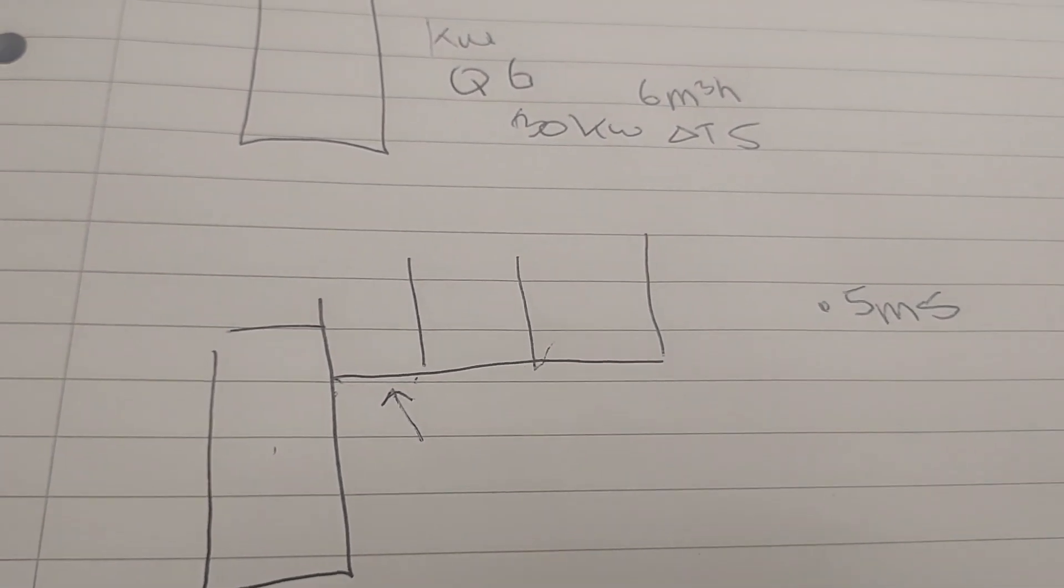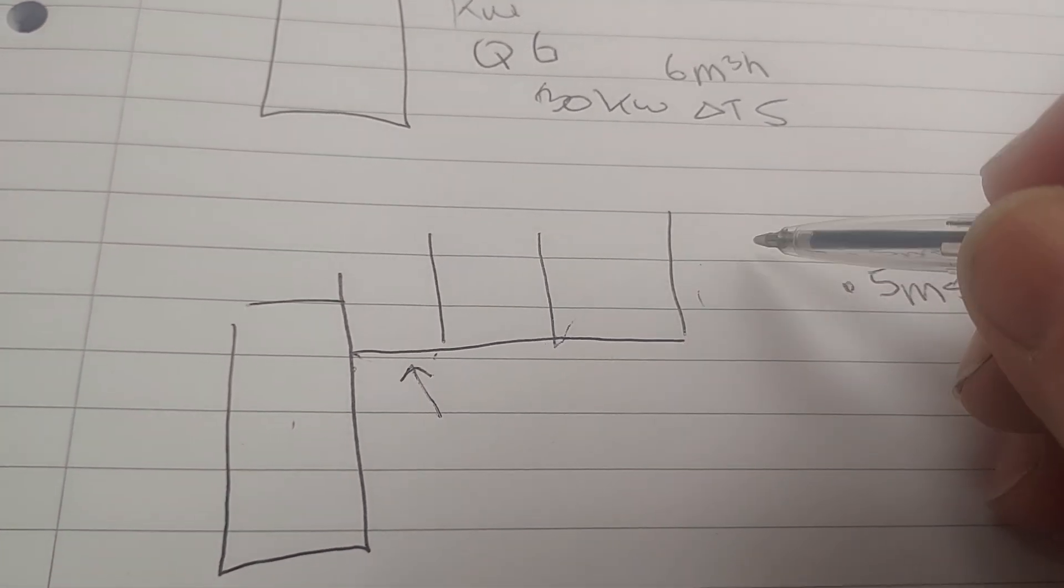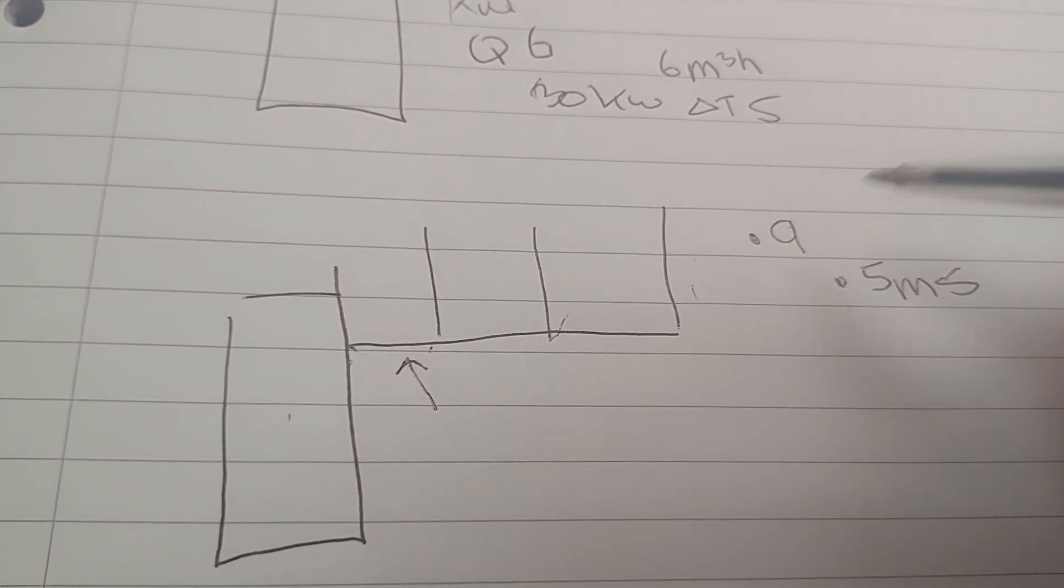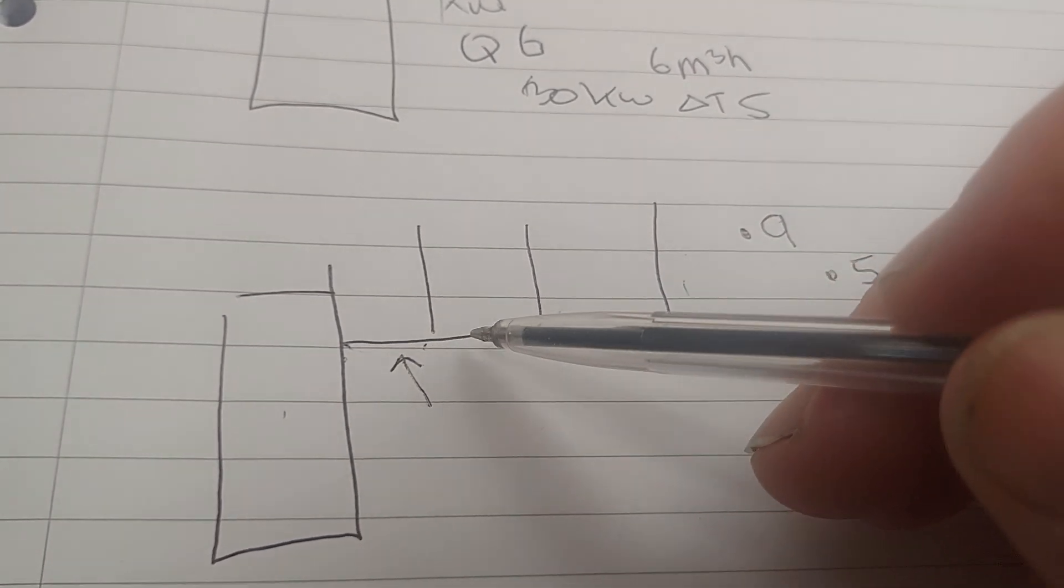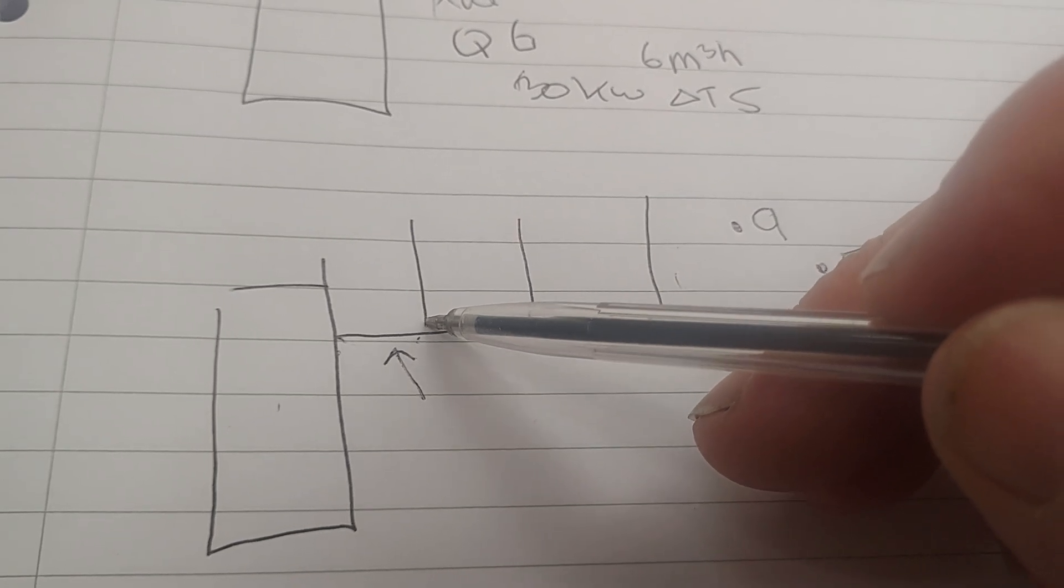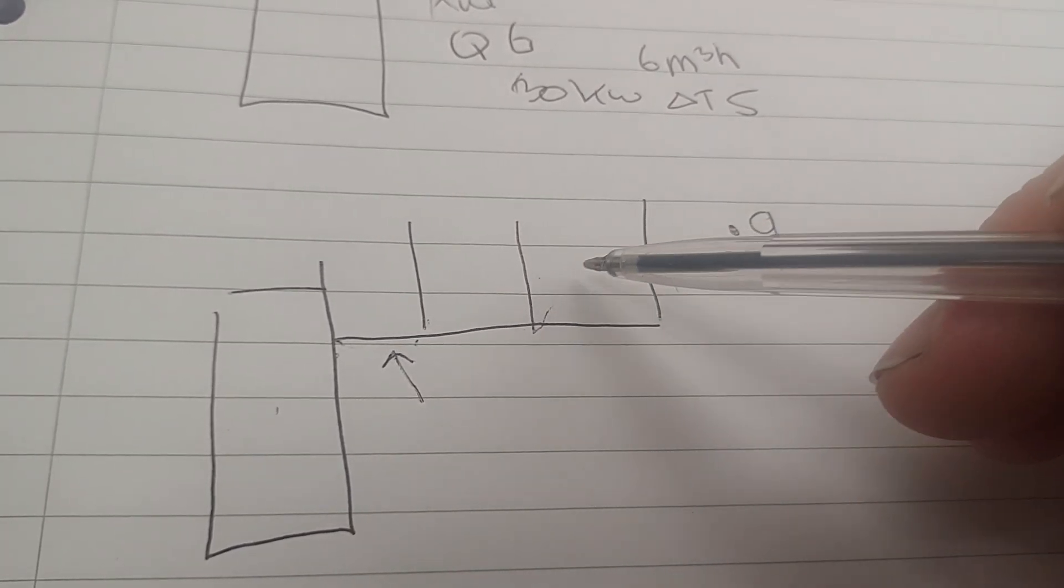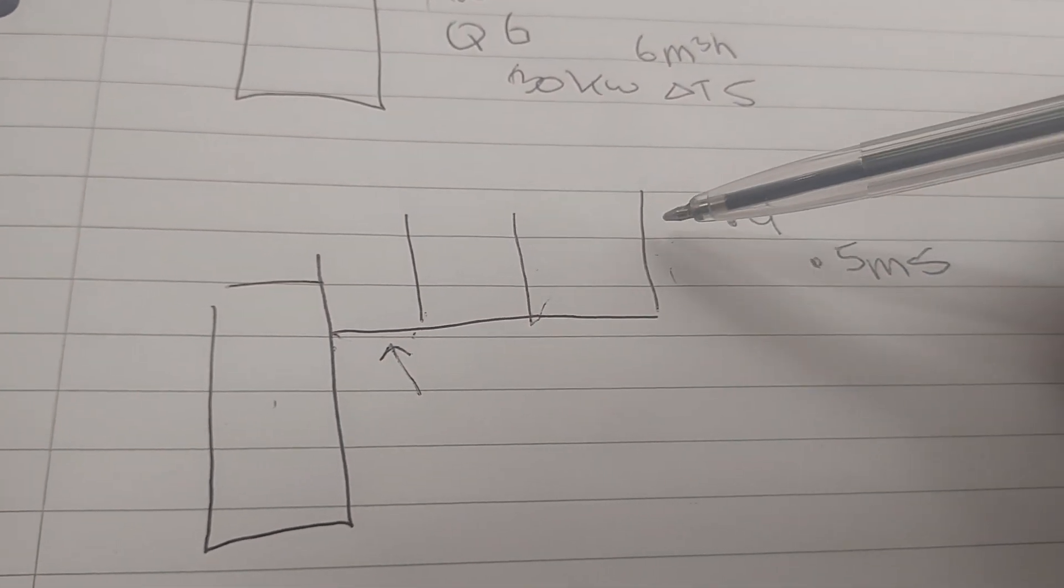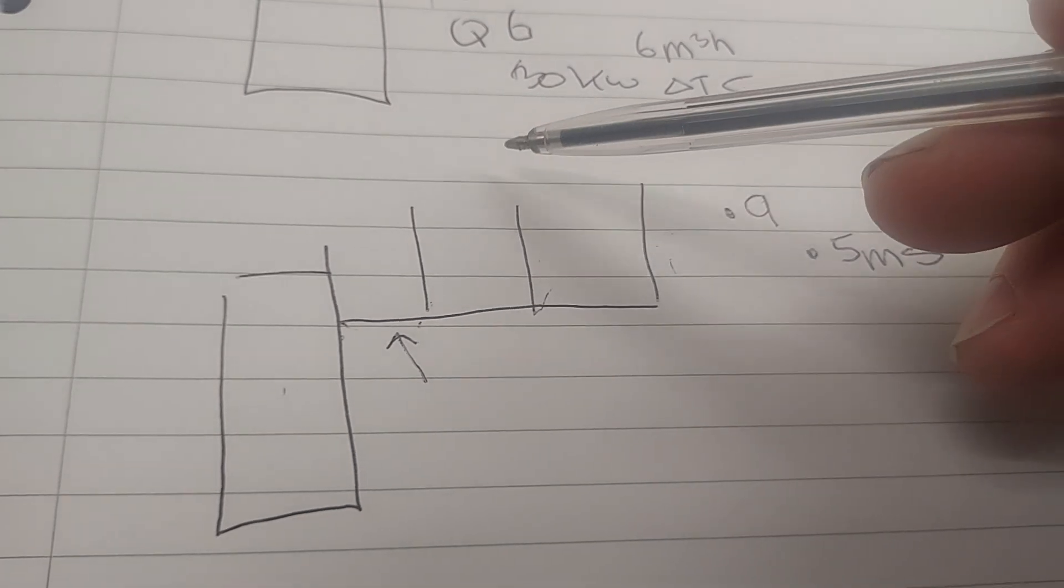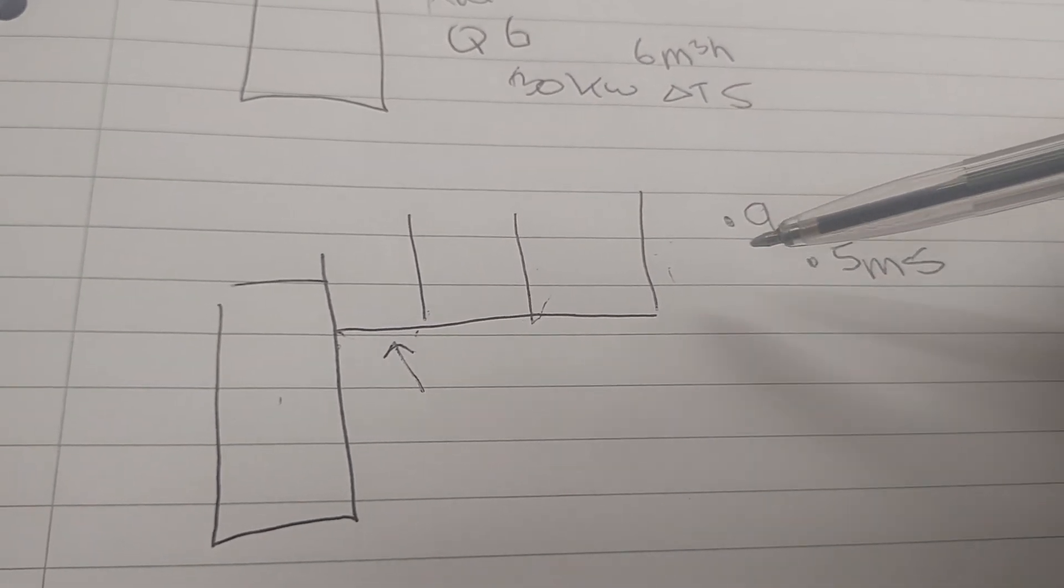Once we're into these pipes, the target velocity here is 0.9. It looks very strange sometimes. You could put a 35mm pipe in here because of the load of all three circuits, and then in theory you'd be coming off in 22 here, probably down to even 15 down here. I don't ever go into 15 because it looks strange, but most of the valves I'm using are half inch.